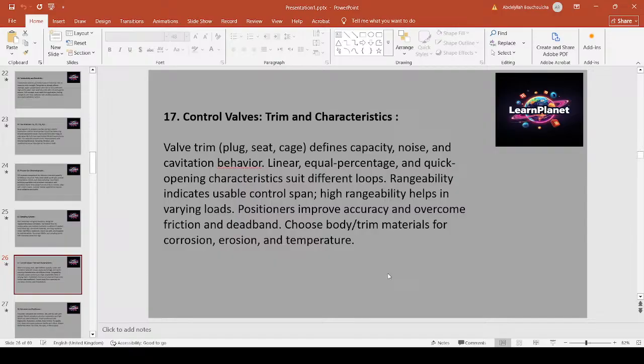Control valves, trim and characteristics. Valve trim, plug, seat, cage, defines capacity, noise, and cavitation behavior. Linear, equal percentage, and quick opening characteristics fit different loops. Rangeability indicates usable control span. High rangeability helps in varying loads. Positioners improve accuracy and overcome friction and dead band. Choose body and trim materials for corrosion, erosion, and temperature.